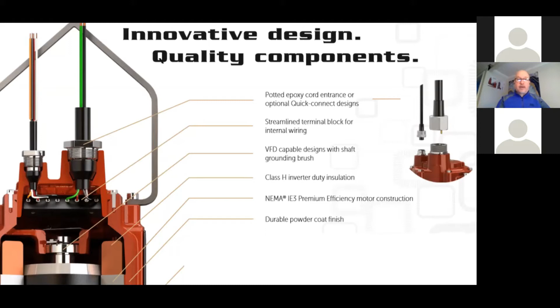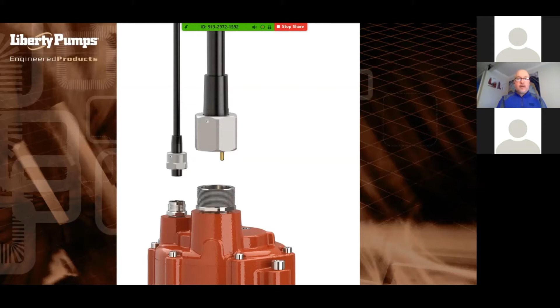Premium efficient motors, durable powder coat finish. Here we have a shot of the quick connect cords for both the control cord and the sensor cord, power cord. And these are stainless steel nuts with a rubber grommet compression fitting here that we've used this design for many years on the smaller pumps that we've sold. The difference mainly being the stainless steel nut, and then we do use a set screw here as well. We've had some people question whether vibration or something like that could loosen that nut up. So we overcome that by using the set screw that can tighten that or keep that nut locked down.